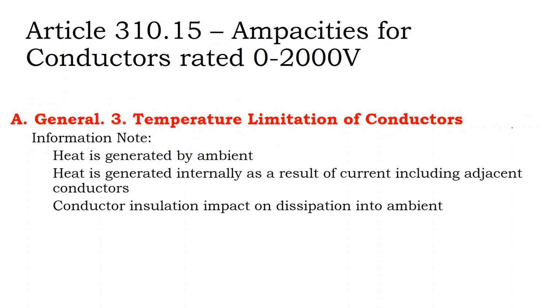And so you might get some better constraints, particularly with your temperature conditions, because whereas the solar installer designing by the chart has to use the harshest applicable assumptions, your engineer might be able to say, well, actually, the true voltage of the system is not going to exceed this much, so you don't need to use this wire. That's over engineering. Then again, there's value in over engineering solar.